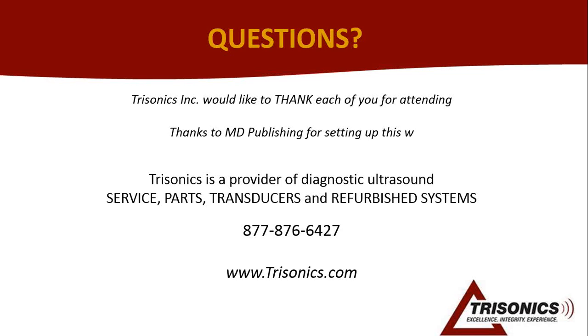That sounded great. Is there a specific tool for transducer calibration? The only real tool would be a phantom. It is the accepted tool. Those of us that have been doing this a long time, we can all complain and say phantoms aren't perfect, and they're not. And there's reasons that they're not perfect, but still, when it comes down to it, it is the accepted tool for checking to see that your transducer's measuring correctly and that kind of thing.